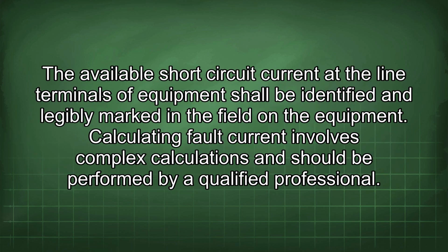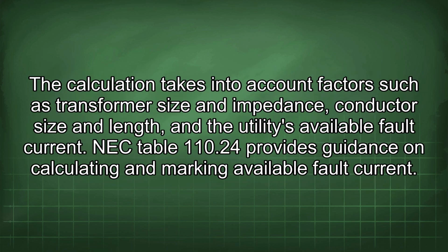The available short circuit current at the line terminals of equipment shall be identified and legibly marked in the field on the equipment. Calculating fault current involves complex calculations and should be performed by a qualified professional. The calculation takes into account factors such as transformer size and impedance, conductor size and length, and the utility's available fault current. NEC Table 110.24 provides guidance on calculating and marking available fault current.